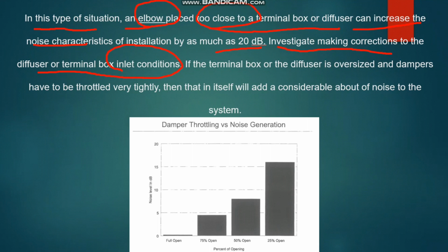Sometimes at the time of the design drawing it will not be there, but when we go to the site, due to clashes with other utilities, we will provide the elbow. If you have that type of situation, this can increase the noise by as much as 20 decibels. And second thing, if the terminal box or diffuser is oversized and the damper has to be throttled very tightly, this is the important thing, so correcting it will reduce the noise of the system.